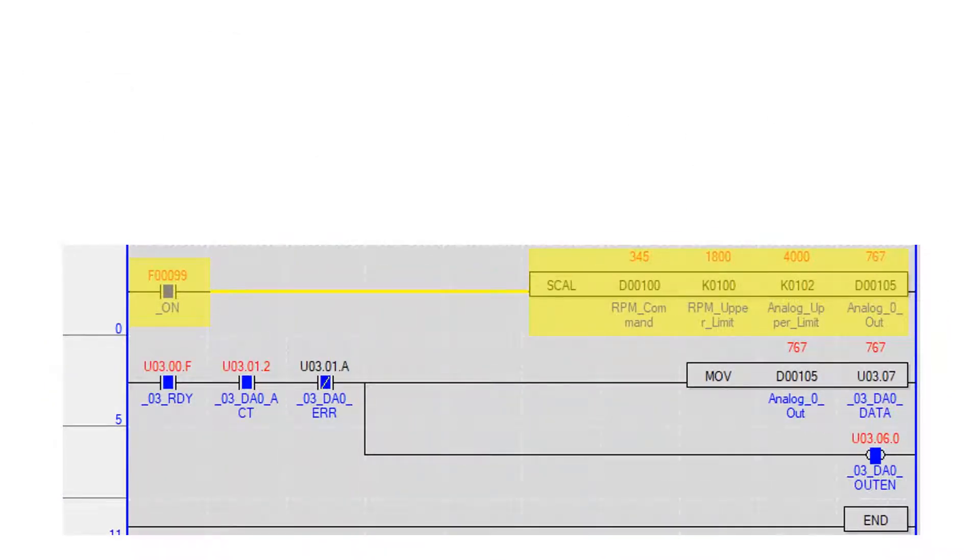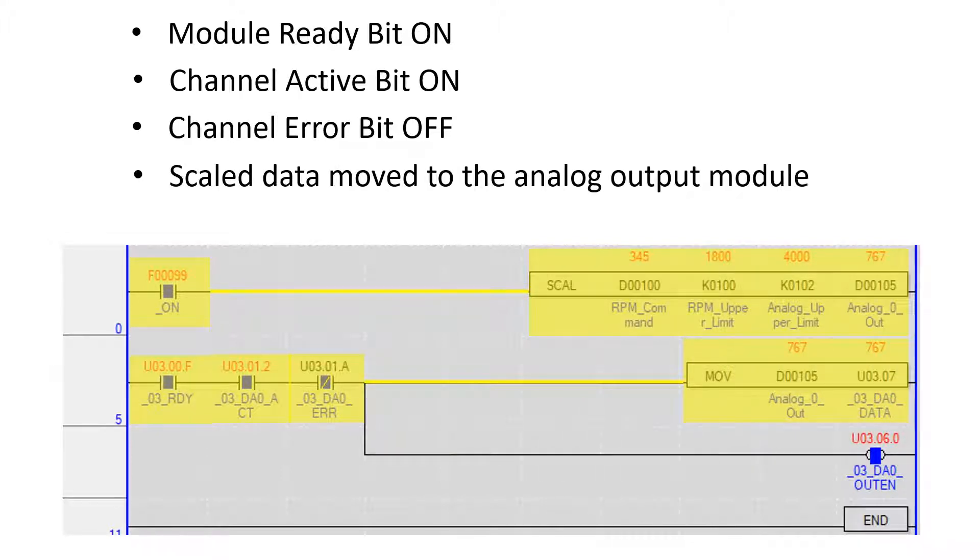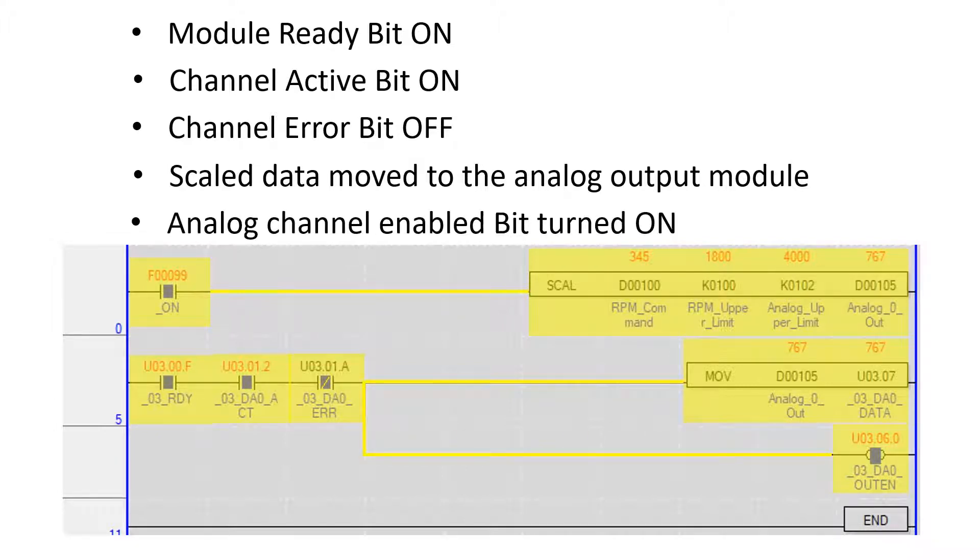To output the analog voltage, three permissive bits are used. The module ready bit and analog output channel 0 active bit must be on. The analog output channel 0 error bit must be off. If the permissive conditions are true, the scaled motor speed value is moved to the analog output channel to output voltage to the VFD. The output channel enable bit must be turned on in order to output analog voltage.